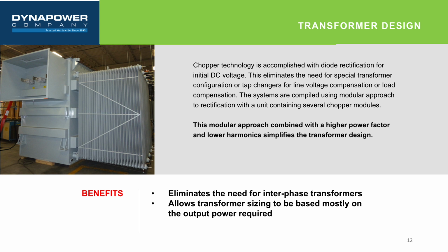Chopper supplies can also tolerate unbalance between 2 secondaries while maintaining optimum harmonic cancellation without the use of IPTs, so K-factors are lowered due to reduced current harmonics. Chopper technology is a modular approach to rectification with a unit containing several chopper modules. The output of each chopper module is electronically regulated. This modular approach, combined with a higher power factor and lower harmonics, simplifies transformer design by eliminating the need for interphase transformers between the outputs of each parallel chopper system module.